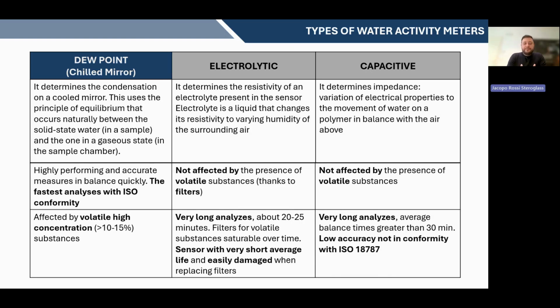Then you have the electrolytic sensor that determines different characteristics of an electrolyte. It measures in a quite longer time, so in this case you will need between 20 to 25 minutes to run a test. So you will need more time to perform the same test as you made on a chilled mirror. It can be not affected by volatiles, but only if you have the right filters to cover the sensor, and these filters are saturable over time, so you need to change them, and even the sensor itself needs to be changed quite frequently, and it has a certain cost.